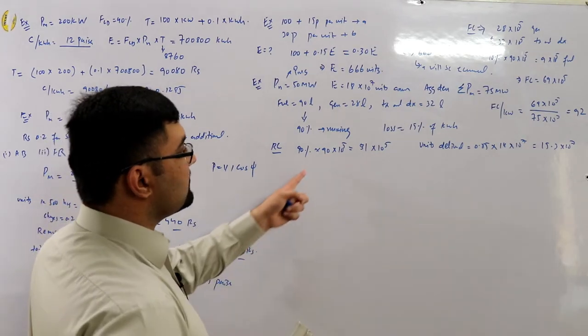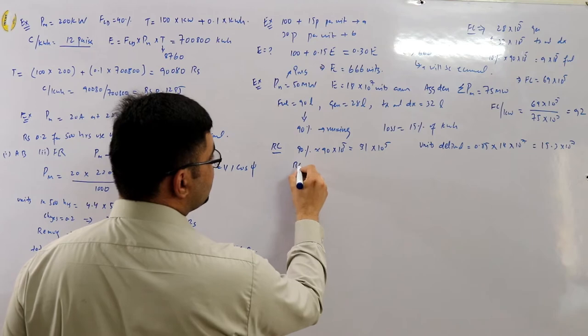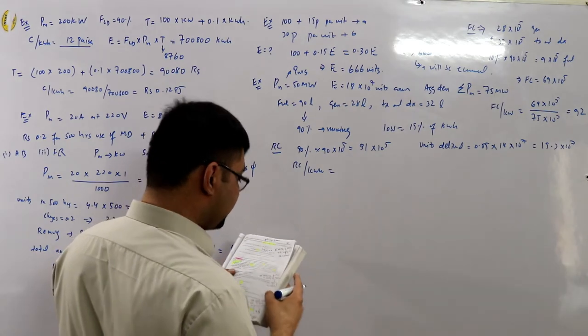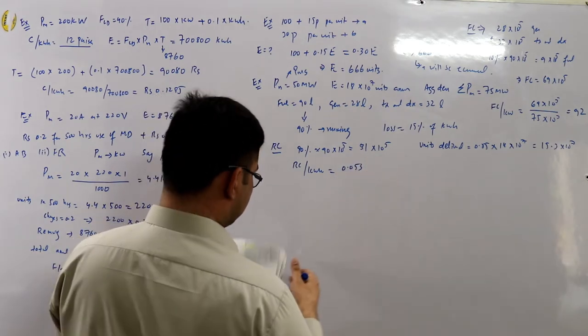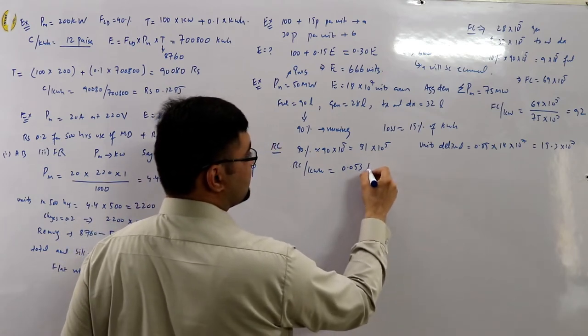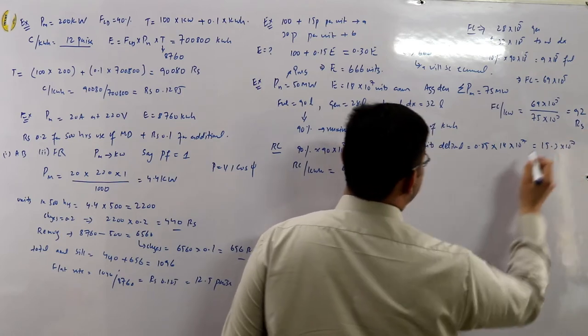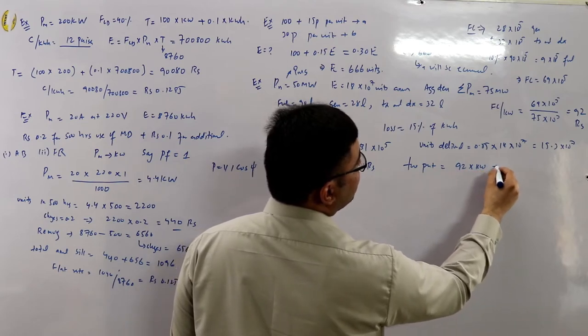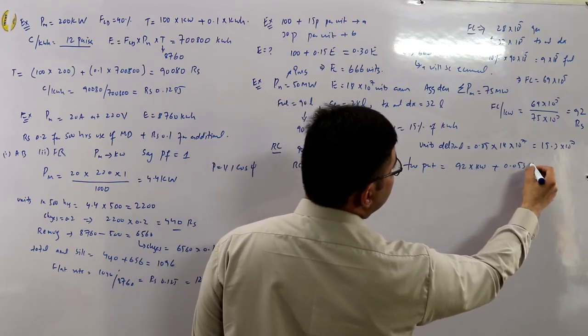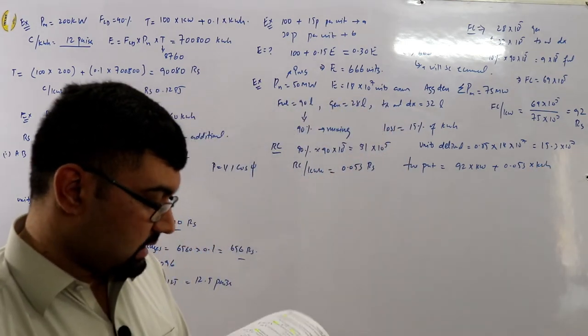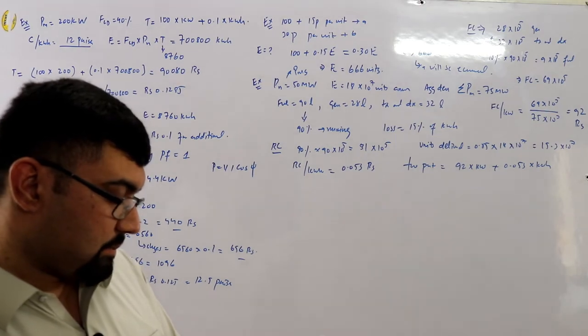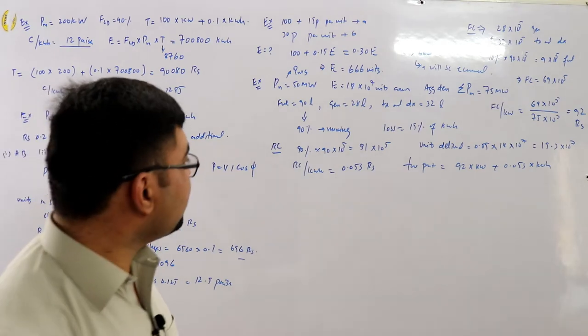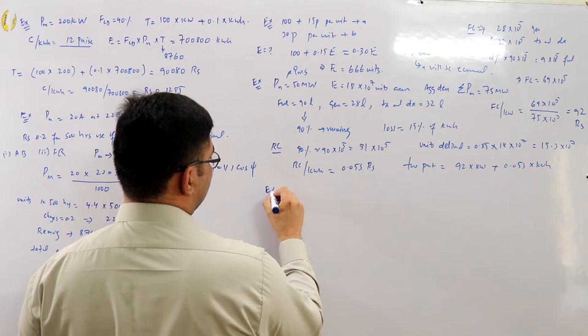Running charges per kilowatt hour = 81 × 10⁵ / 15.3 × 10⁷ = 0.053 rupees, or 5.3 paisa per kilowatt hour. The two-part tariff is therefore: rupees 92 per kilowatt plus 0.053 rupees per kilowatt hour.